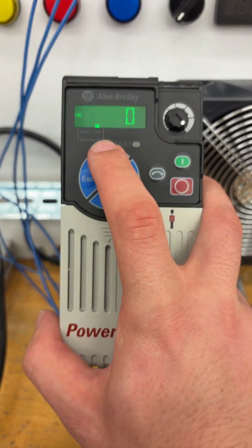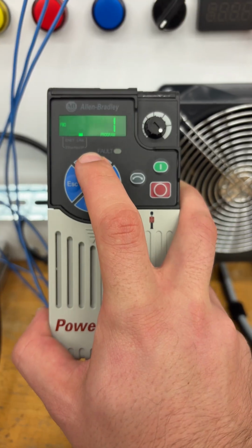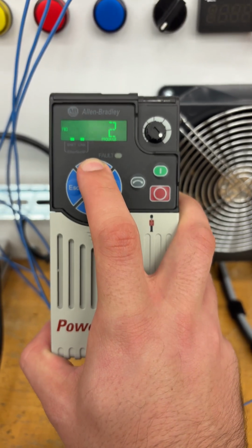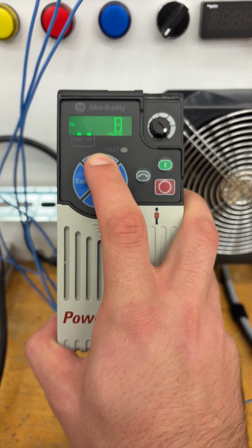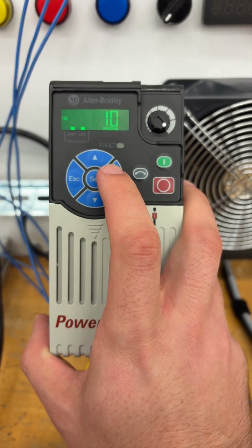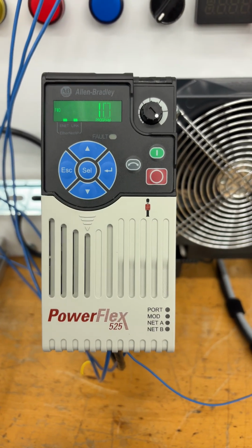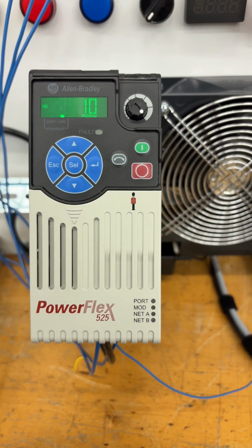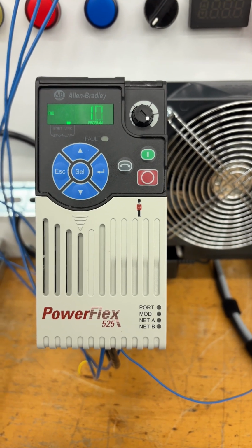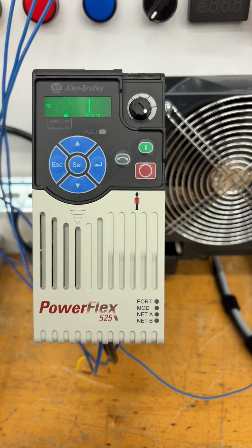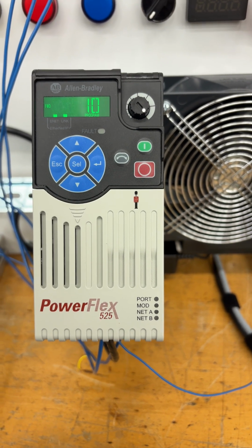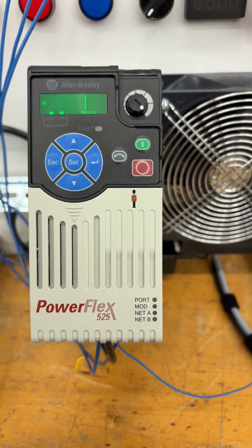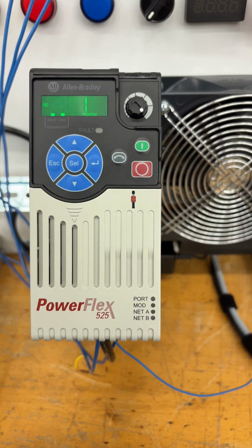The more I apply, so I can apply anywhere from 0 to 100, the more it is going to smooth it out. And you would use this for applications where, let's say, you want to start a conveyor belt that's carrying a delicate object, and you don't want to start it too hard and cause that object to fall over and break. This creates a very gentle acceleration, but it does extend the total time.